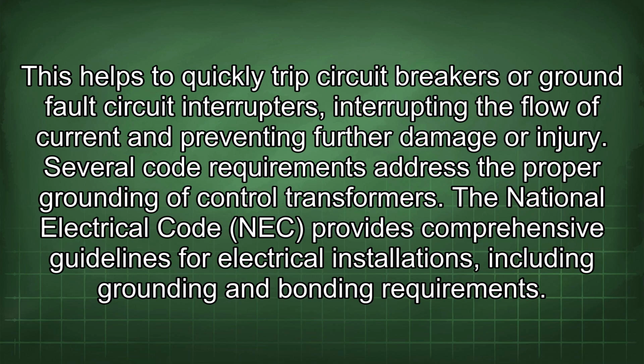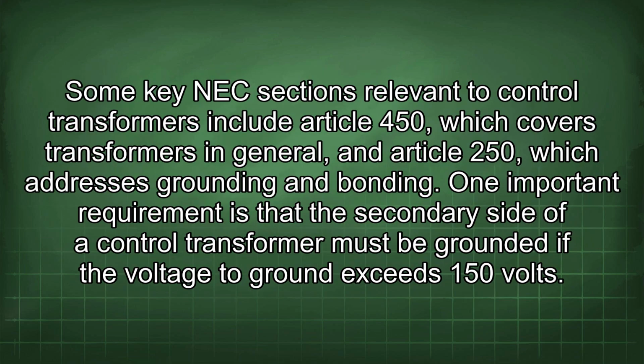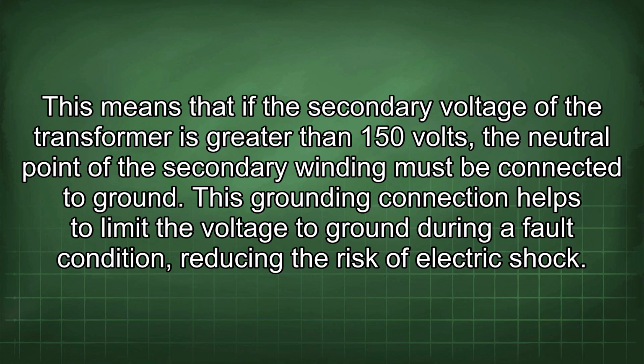The National Electrical Code (NEC) provides comprehensive guidelines for electrical installations, including grounding and bonding requirements. Some key NEC sections relevant to control transformers include Article 450, which covers transformers in general, and Article 250, which addresses grounding and bonding. One important requirement is that the secondary side of a control transformer must be grounded if the voltage to ground exceeds 150 volts. This means that if the secondary voltage of the transformer is greater than 150 volts, the neutral point of the secondary winding must be connected to ground. This grounding connection helps to limit the voltage to ground during a fault condition, reducing the risk of electric shock.